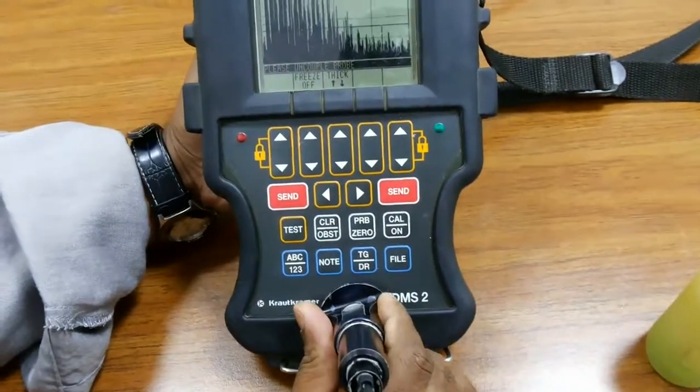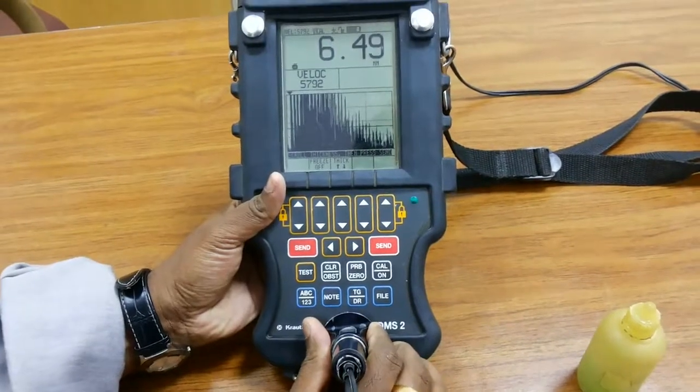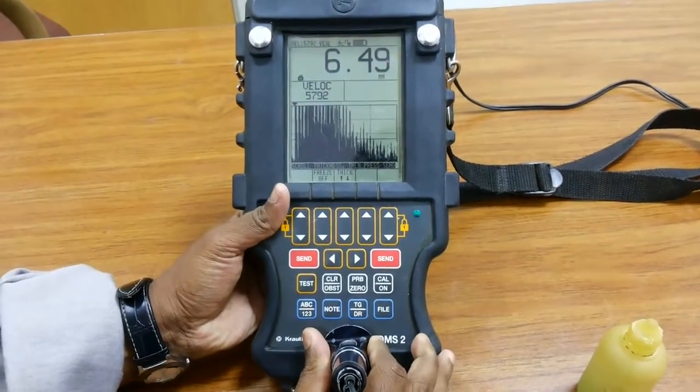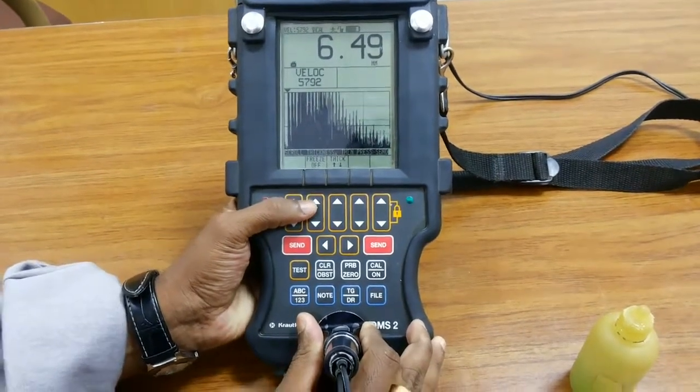Now place the probe on the coupling. It's showing 6.49mm. This block is 6.5mm thickness, so we need to adjust it.